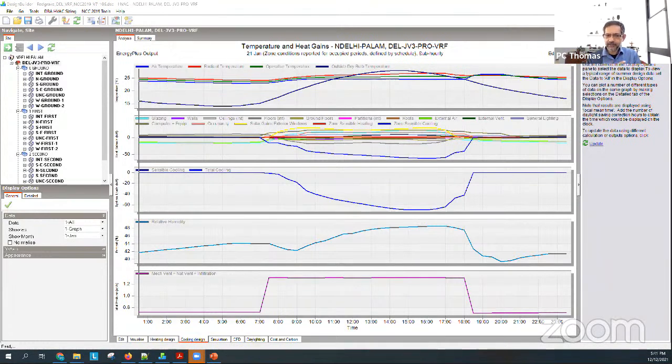So if you've got a chilled beam system, you have to make sure that your construction is quite tight. You don't leak much outside air, and you lose things like an economizer cycle. Again, it's too much to cover in one quick session. You need to know some HVAC to do that. Please talk to your seniors or your project managers for some of these things.